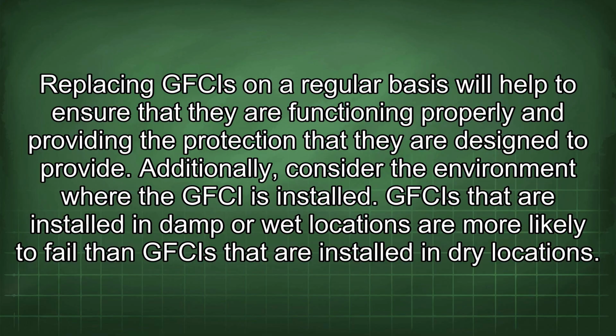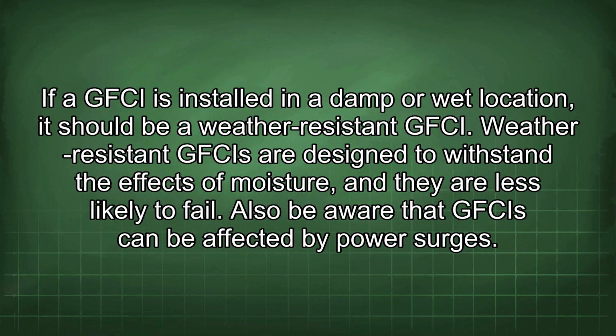Additionally, consider the environment where the GFCI is installed. GFCIs that are installed in damp or wet locations are more likely to fail than GFCIs that are installed in dry locations. If a GFCI is installed in a damp or wet location, it should be a weather-resistant GFCI. Weather-resistant GFCIs are designed to withstand the effects of moisture, and they are less likely to fail.